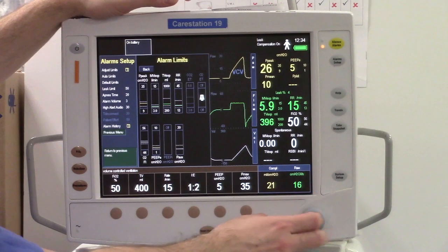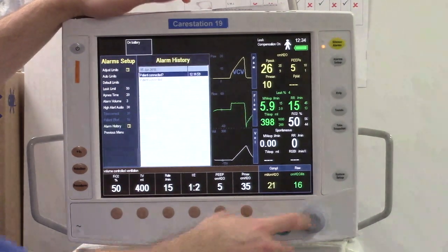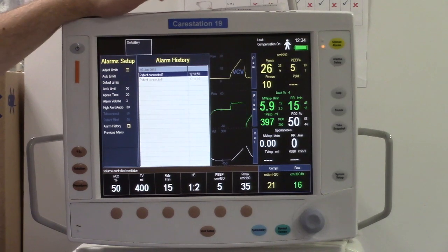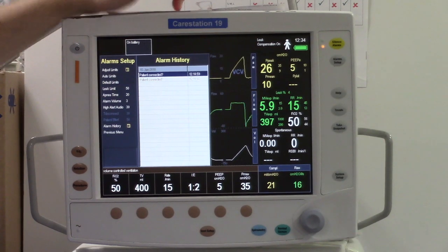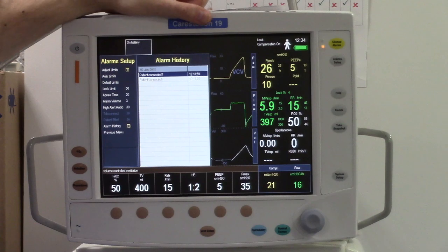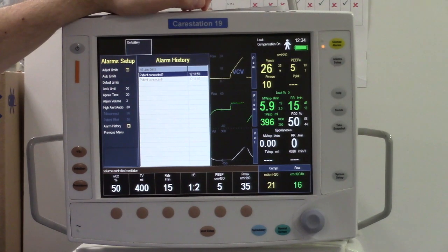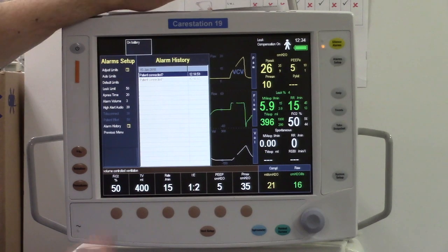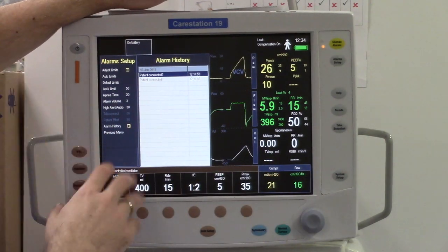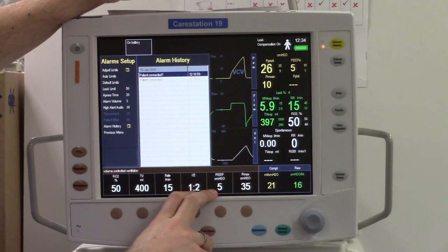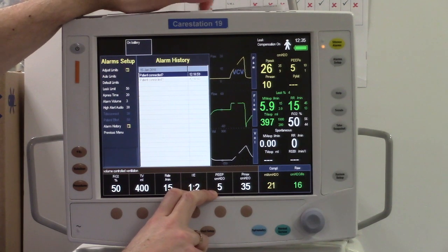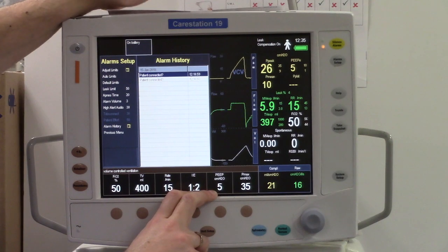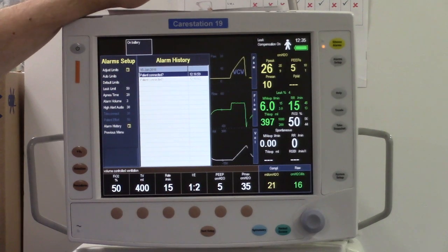And then the other thing I was telling you about in the alarm setup is the alarm history. So here you can go back and see what kind of alarms you had before. For example, your ventilator was alarming, but you were in a different bed space, you didn't have time to respond quickly and have a look at what's happening with the ventilator, and the alarm disappeared. So you can go back in the history and have a look. Or you had a specific alarm that is bothering you, or you feel concerned about something, you have to call the doctors if it's to do with the patient and show them this alarm, or if it's to do with the ventilator, you show us this alarm, yeah?